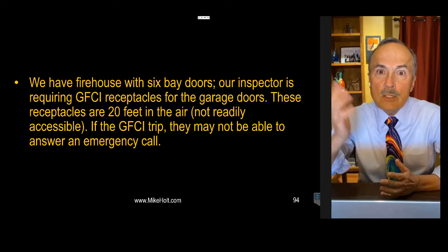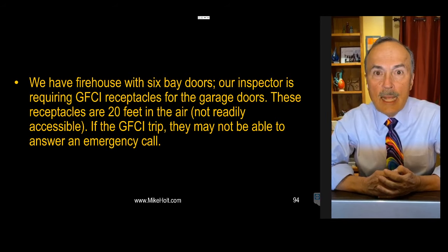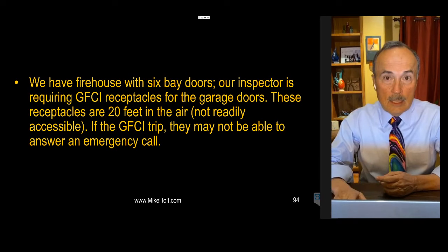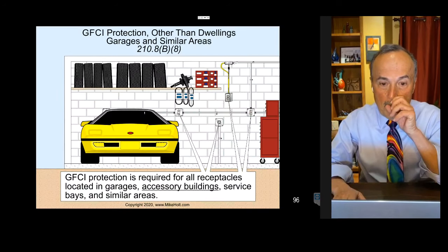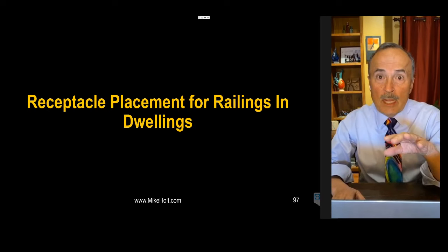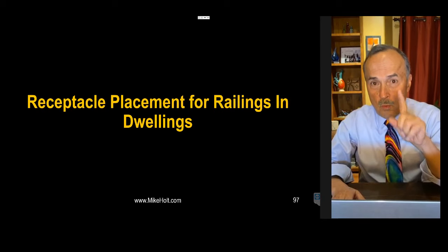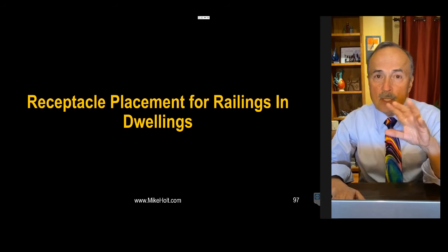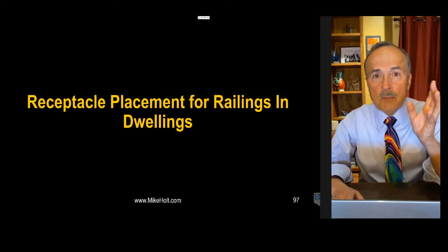So back over to the question. Do those receptacles in the firehouse have to have GFCI protection? Yes. Could you use a GFCI receptacle 20 feet off the ground? Of course not. So what do you do? Just put a GFCI breaker. That makes the breaker guys happy. So, not that complicated.